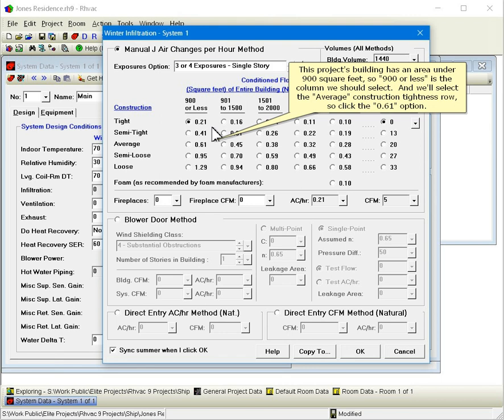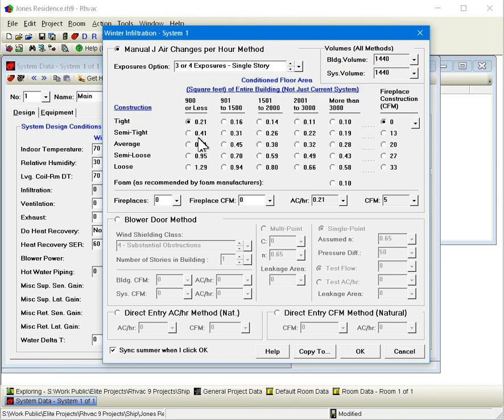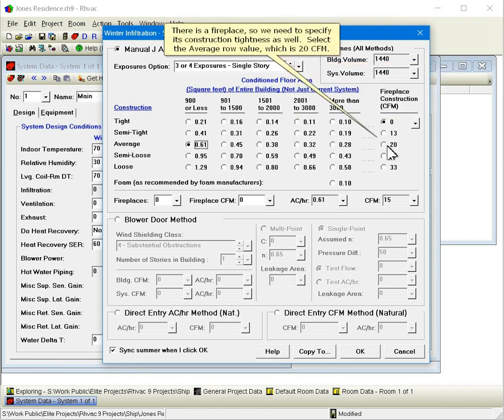And we'll select the average construction tightness row, so click the 0.61 option. There is a fireplace, so we need to specify its construction tightness as well. Select the average row value, which is 20 CFM. There is one fireplace, so select the 1 row.